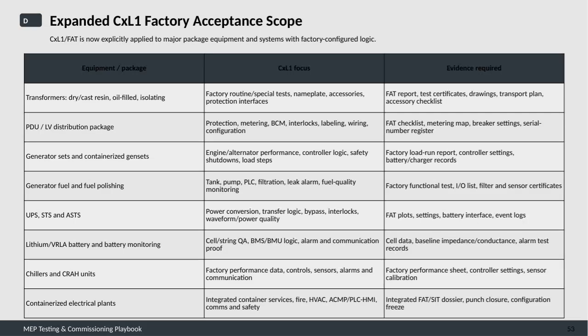Here we have the expanded CxL1 factory acceptance testing, or FAT, scope, now applied explicitly to major equipment packages that come with factory-configured logic. This means that for each key piece of equipment, specific tests and evidence are required before it leaves the factory. For transformers, whether dry, cast resin, oil-filled, or isolating types, the focus is on routine and special factory tests, along with verifying nameplates, accessories, and protection interfaces. The evidence includes detailed FAT reports, test certificates, drawings, a transport plan, and an accessory checklist.